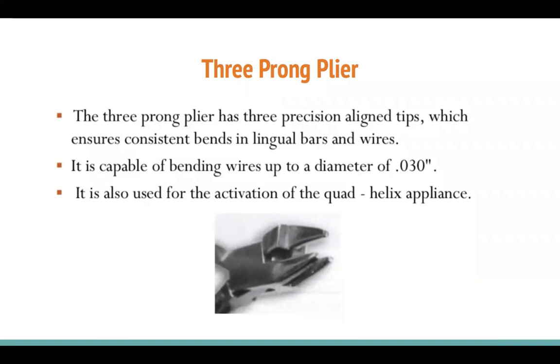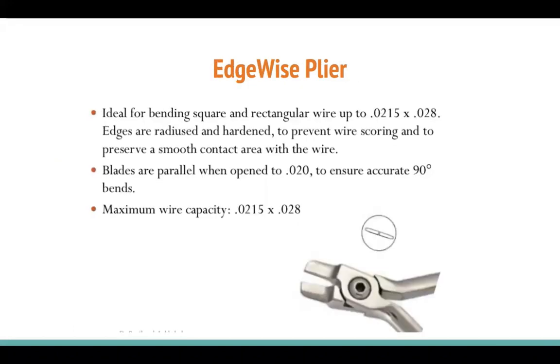The three-point plier is a useful plier used to make retainer wires. It has three precision-aligned tips which ensure consistent bends in lingual bar and wires. It is capable of bending wire up to 0.03 inches in diameter. It is also used for activation of the quad helix appliance — so it can be used both for making retainer wire and for quad helix activation.